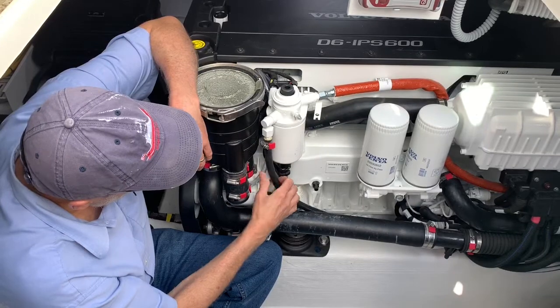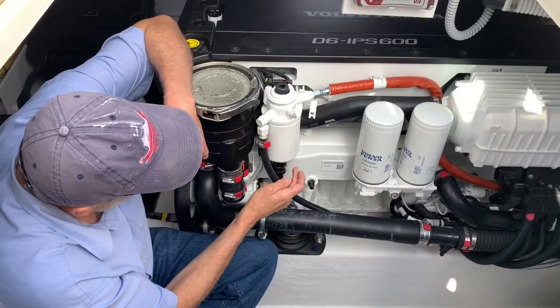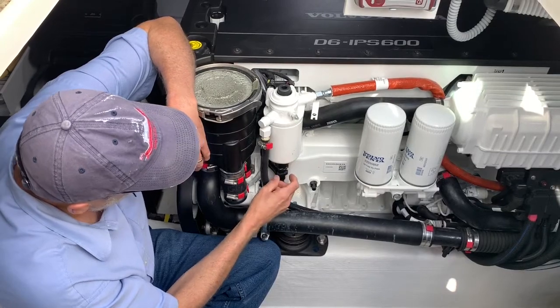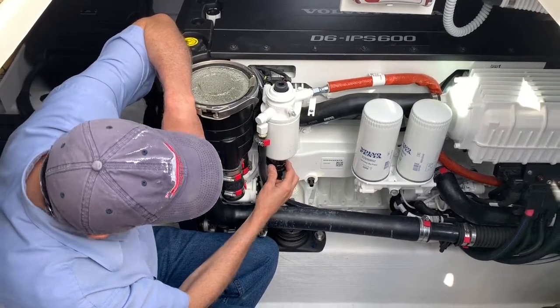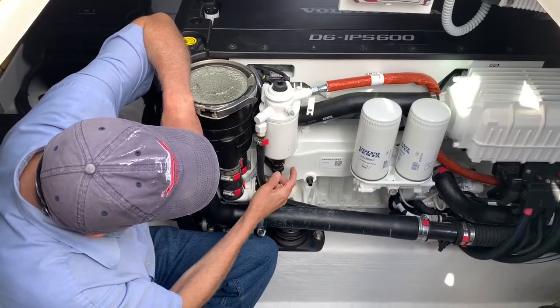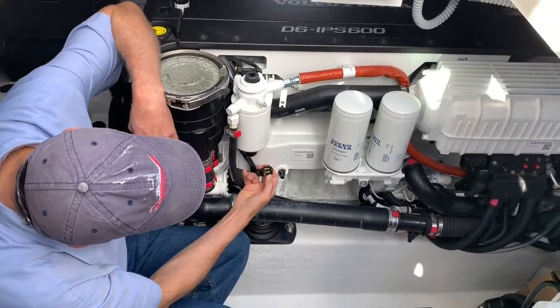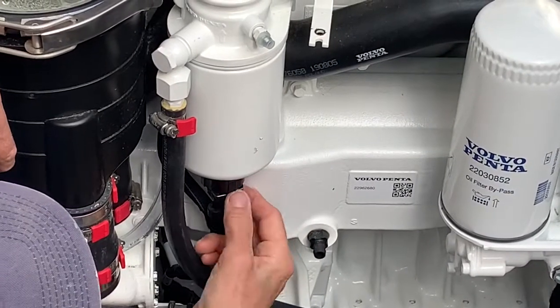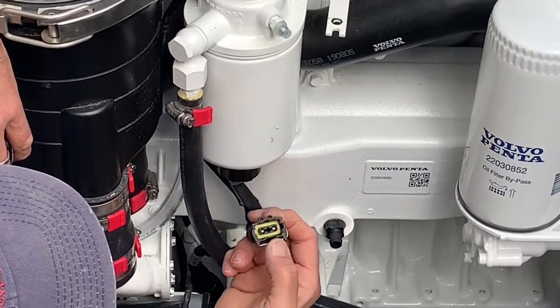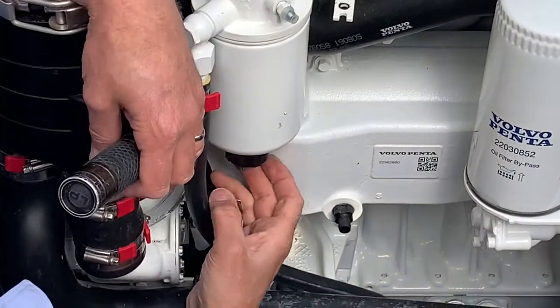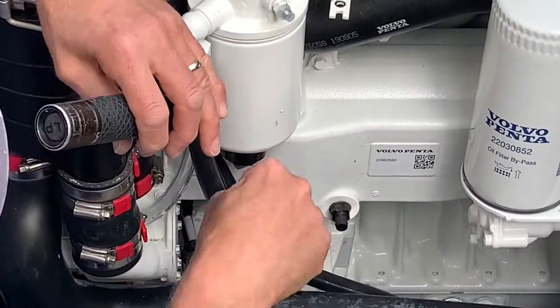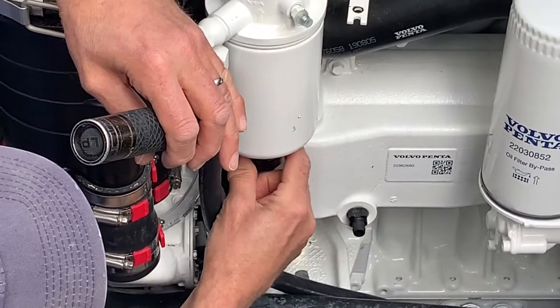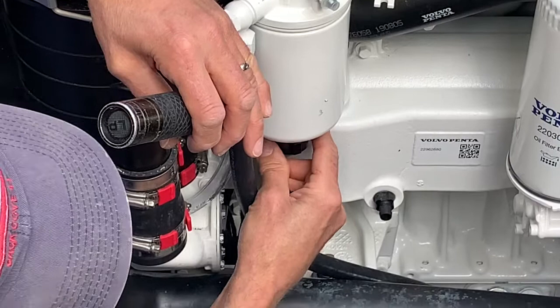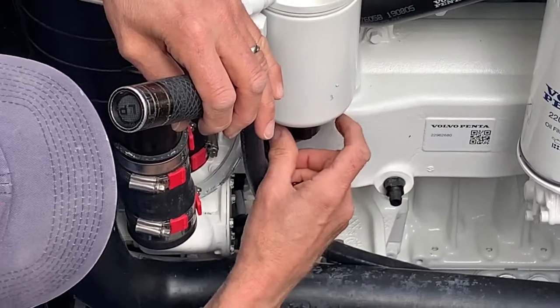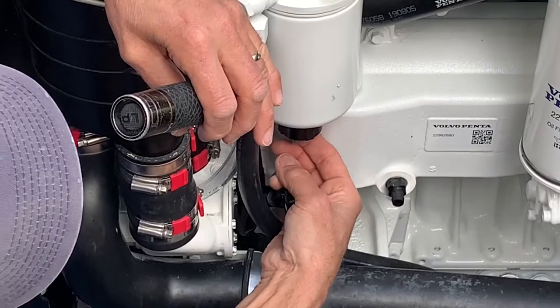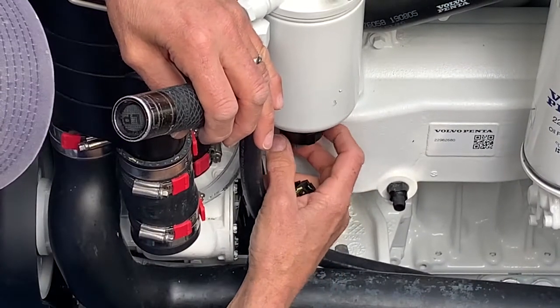So if your water-in-fuel alarm goes off, you need to get the water out of the bottom of this fuel filter. The alarm will be up at the main display. To get the water out, you need to unplug the sensor, which is here. On this plug, you just push this wire in right here and pull it out. Now, in the back here, you may not be able to see it, is a small drain hole built into this big threaded knob here. All you need to do is loosen this. You don't need to take this knob all the way out. Just loosen it a turn or two, and fuel will drain out of the little bleed hole in the bottom. You capture it in a paper cup.